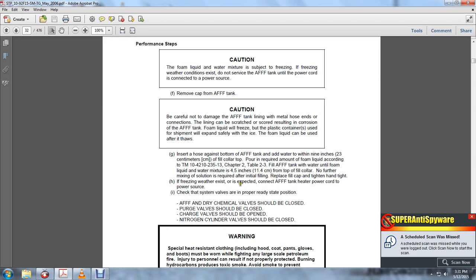If freezing weather exists, connect the AFFF tank heater power cord to the power source. Check the system valves in the properly ready position. The AFFF dry chemical valve should be closed. Purge valve should be closed. Charge valve should be open. Nitrogen cylinder valve shall be closed.